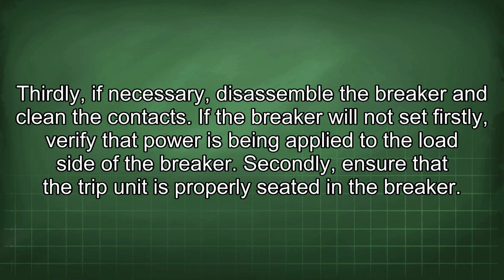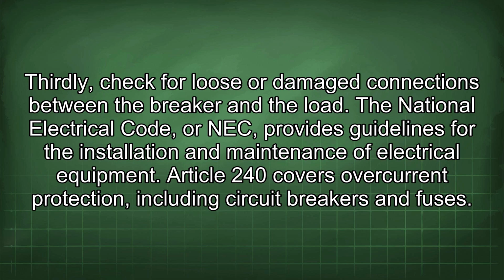If the breaker will not set, firstly, verify that power is being applied to the load side of the breaker. Secondly, ensure that the trip unit is properly seated in the breaker. Thirdly, check for loose or damaged connections between the breaker and the load.